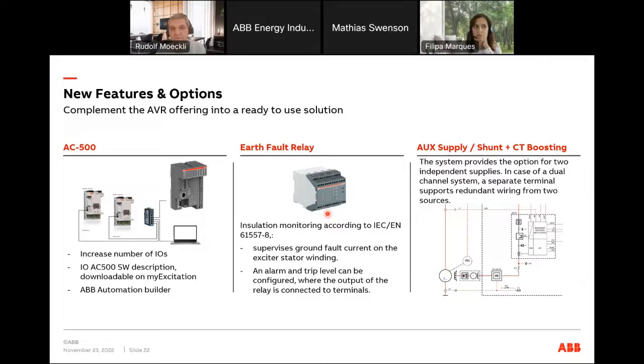Then on the plate itself, it has this earth fault relay from ABB. This is an option, since that device is quite expensive, but it will supervise the excitation field of the machine - not the field, but the stator winding of the exciter machine. As mentioned before, auxiliary supply, shunt supply, and CT boosting are options you can have on the plate.